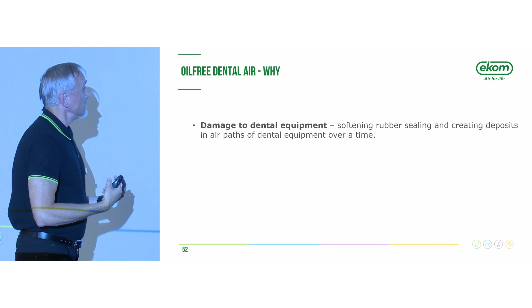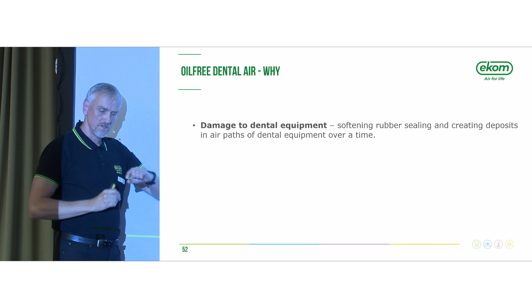Oil-free dental air, why? If somebody uses an old oil compressor, oil is used or was used in the past for lubrication. Oil consists of very light particles which may continue through the system, and these light particles may damage dental equipment - they soften rubber sealing and create deposits in air paths of dental equipment over time.